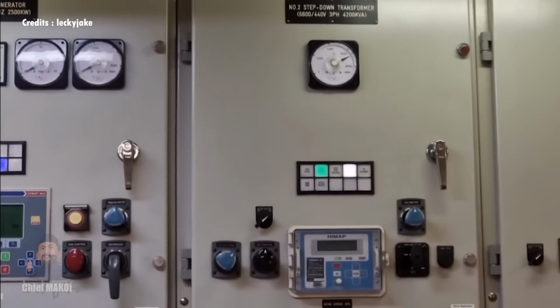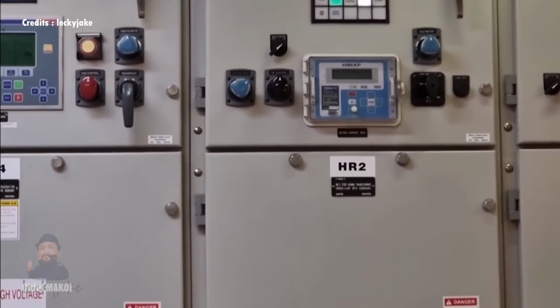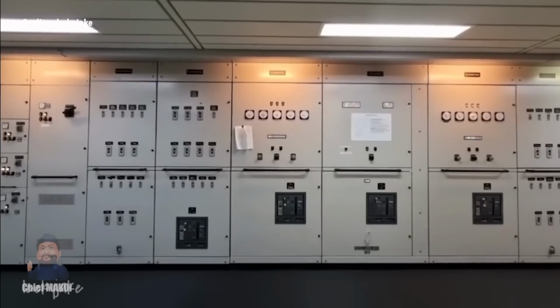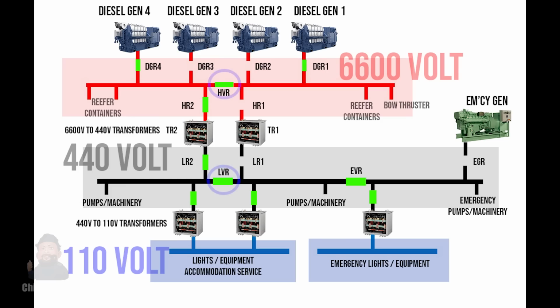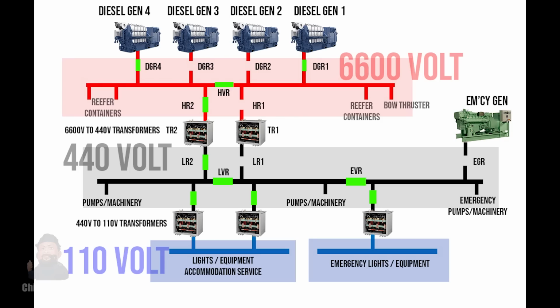These ships use high voltage installations because of the advantages of having a lower current, resulting in reduction of the size of the generators, motors, and cables, saving of space and weight, and lower power losses, among other things. Now, in both cases, there are bus ties on the bus bars. These are designed to be in closed position during normal operation. They are only switched to open position in case there is a need to isolate one side for maintenance purposes. In ships having a similar setup with the Dali, having the bus ties open will mean using two generators, one connected to each side of the high voltage bus, and both of the transformers TR1 and TR2 can be used at the same time, providing 440 volt electricity to their respective switchboards independently of each other.